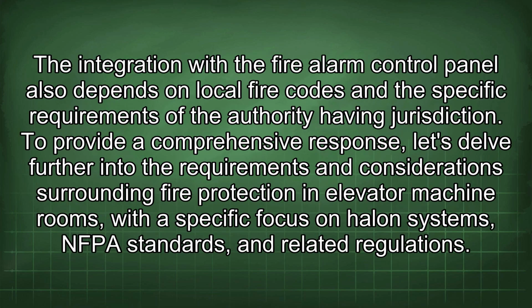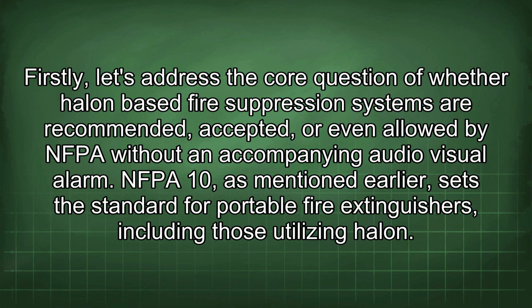The integration with the fire alarm control panel also depends on local fire codes and the specific requirements of the authority having jurisdiction. To provide a comprehensive response, let's delve further into the requirements and considerations surrounding fire protection in elevator machine rooms, with a specific focus on Halon systems, NFPA standards, and related regulations. Firstly, let's address the core question of whether Halon-based fire suppression systems are recommended, accepted, or even allowed by NFPA without an accompanying audio-visual alarm.